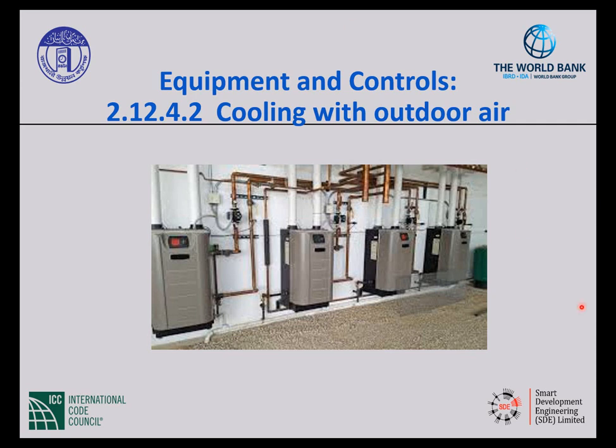What is this talking about? This is talking about not cooling with outside air. Sorry. This is talking about controls to reduce the amount of energy used when the building isn't requiring all of the load to be used. So if I have a building and it says, okay, in order to heat or cool this building, I'm going to need 4 boilers. So I have these 4 pieces of equipment that at the worst load conditions possible, it would take all 4 of them to supply the building.